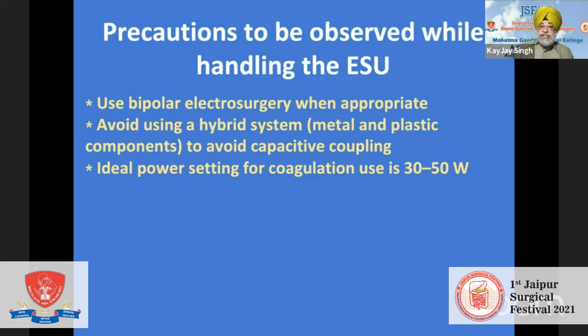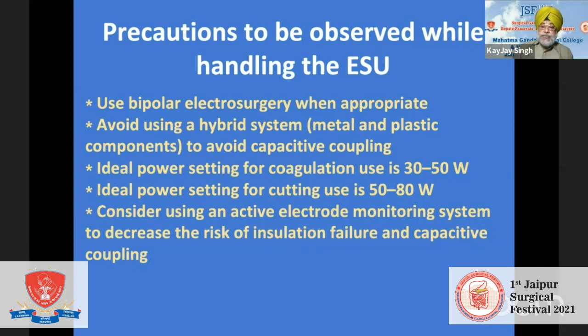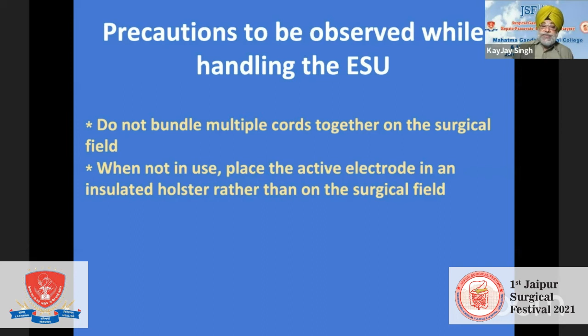The ideal power setting for coagulation, very important for general surgeons, is 30 to 50 watts. The ideal power setting for cutting is 50 to 80 watts. Consider using, and this is something very important, you must invest in this, an active electrode monitoring system in the electrosurgical unit to decrease the risk of insulation failure and capacitive coupling. Do not bundle multiple cords on the surgical field. When not in use, place the active electrode in an insulated holster on the patient rather than directly on the drapes in the surgical field.